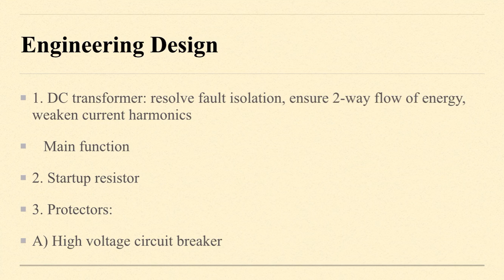And the next is startup resistor. The starting circuit is the unique circuit in VSC HVDC transmission system. Before normal operation, MMC converters need to be charged in order to reduce the disturbance and voltage stress of diodes, which come from the charging current. We choose to connect a charging circuit in series between the MMC converter and transformer.